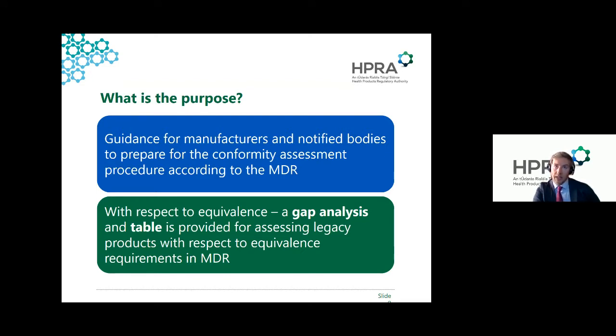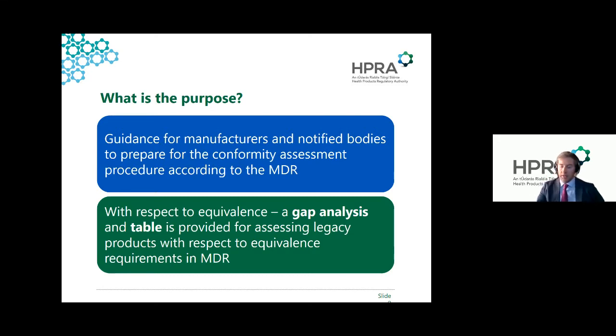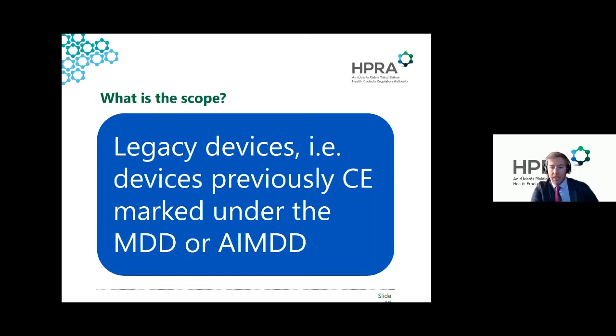The purpose of these two guides is to help manufacturers and notified bodies prepare for conformity assessment under MDR, specifically for legacy products. An important feature of the equivalence guidance is that it provides both a gap analysis and a standardized table — the document runs to about 20 pages. One rationale for needing specific equivalence guidance was that the previous consensus guidance — MEDDEV 2.7/1 revision 4 — and Annex 14 of MDR were drafted in parallel, leading to slight differences that needed to be accommodated and explained.